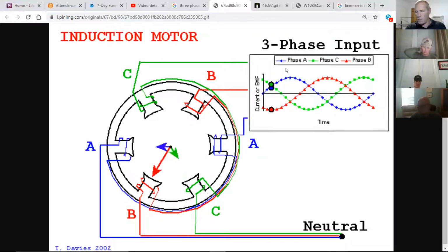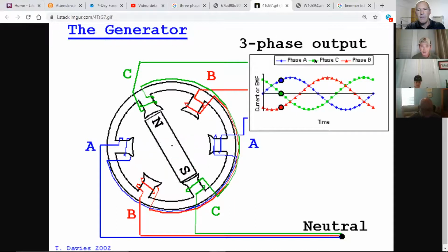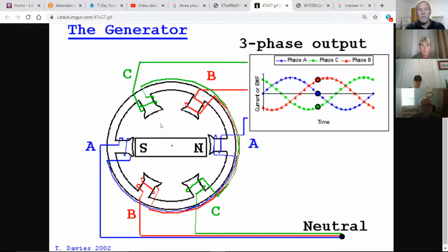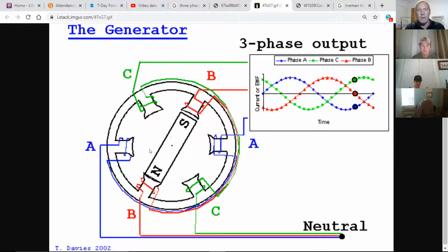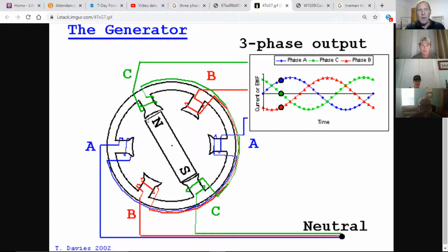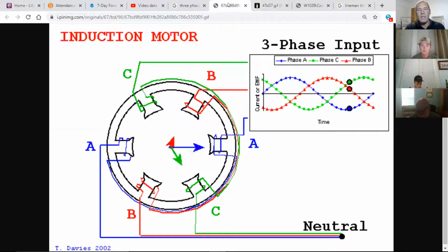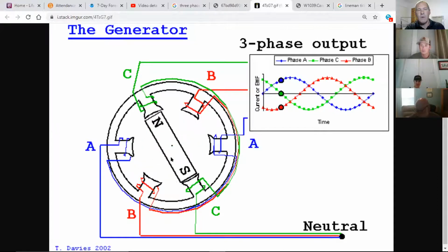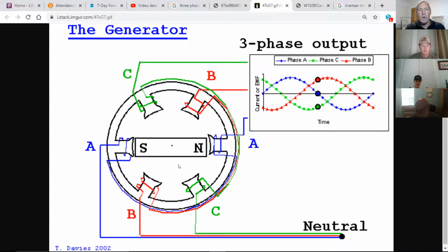You can have different phase rotations anywhere in the world, as long as the generator and whatever you're powering matches. So in my generator here, I have phase A, phase C, phase B. What is my rotation, clockwise or counterclockwise? Clockwise. That's the way my generator is rotating. If I match my motor in the same phase order, A, C, B, what rotation will I have in my motor? Clockwise. I can guarantee you, gentlemen, at the generating station, this is never going to change. All generators go in a clockwise motion.